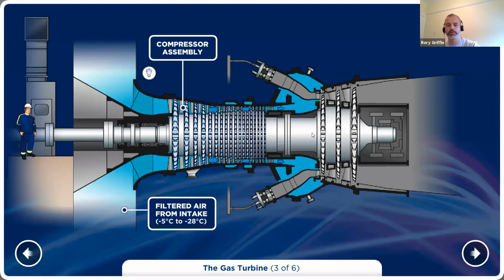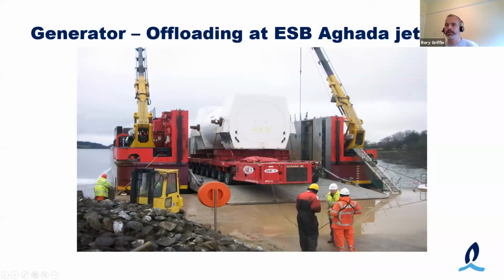So I'll just head back there to the generator itself. That's just a picture of the generator coming off. This is actually the jetty, ESB, so they're very good neighbours to allow Bord Gáis at the time use the jetty to get some of the barged equipment off. So the generator in that, unconnected, would be 280 tons. It's a bit heavier in operation because there's huge losses on the stator winding, so it's actually hydrogen cooled. In operation, it's filled with hydrogen, and you've seals at each end, so you don't want the hydrogen to escape because hydrogen at the wrong purity is lethal.